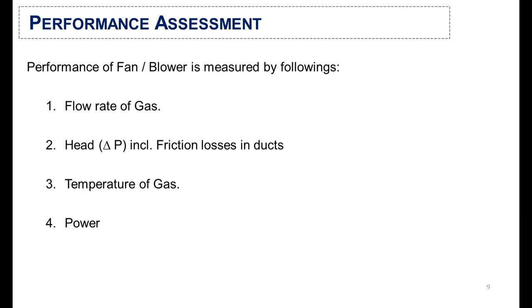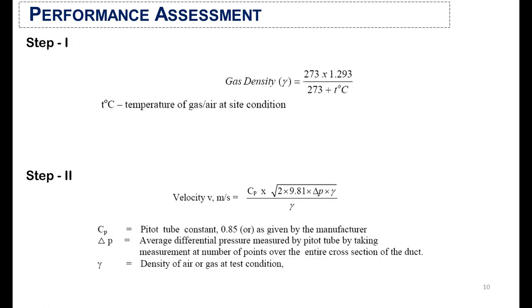The following parameters are used to assess the performance of blowers or fans. First is the flow rate of the gas — at what value the gas is being handled in the fan or blower. Second is the head value — that is the pressure drop at the suction and discharge piping of the blower, which also includes friction losses. Third is the temperature of the gas, and fourth is the power requirement for the fan or blower.